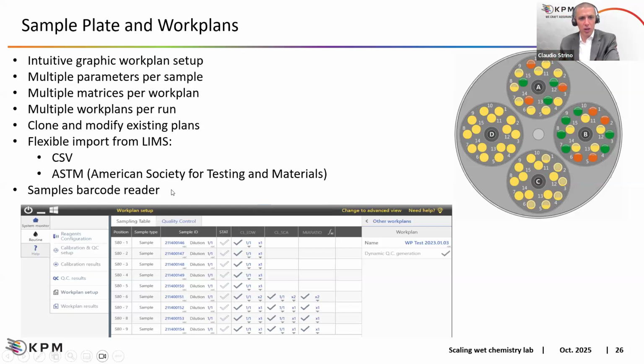Again, the sample compartment is equipped with barcode readers, so we have positive recognition of the samples. And so our operators don't need to load each sample in a specific position, but they can load the samples as they want in the rack. The system will scan and will determine from the barcode label which sample is in which position. When importing from the LIMS, the working table is automatically created. So having the instrument equipped with barcode readers, we can also skip any human error concerning liquid positioning on board.